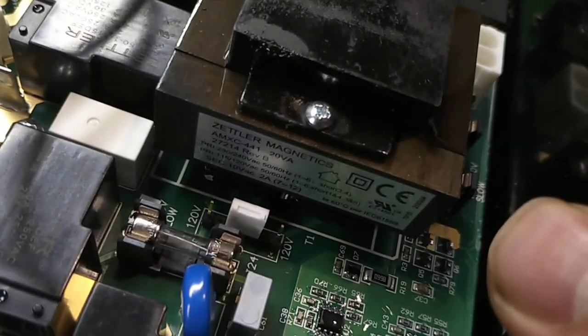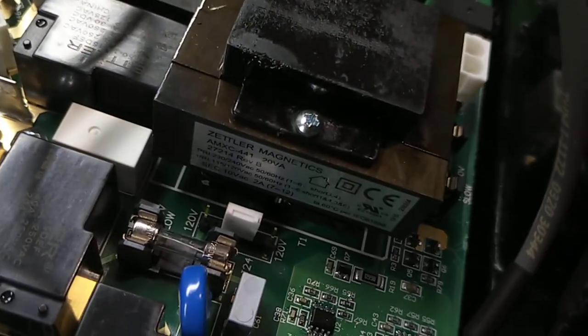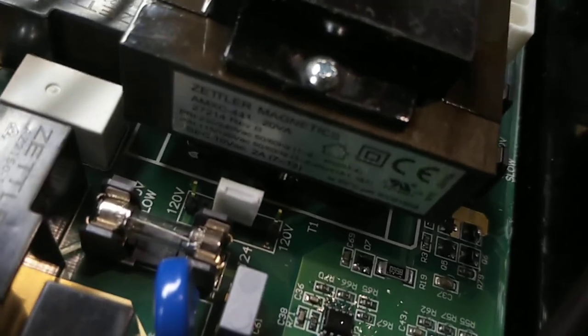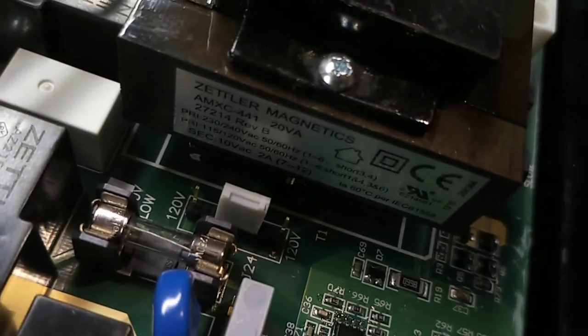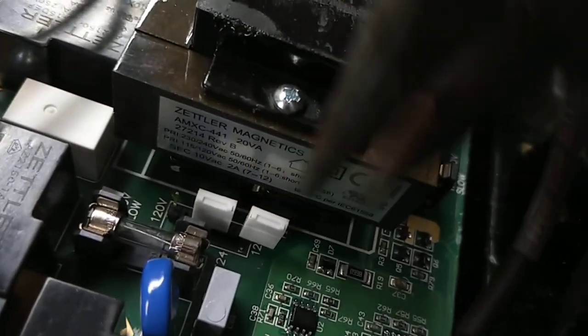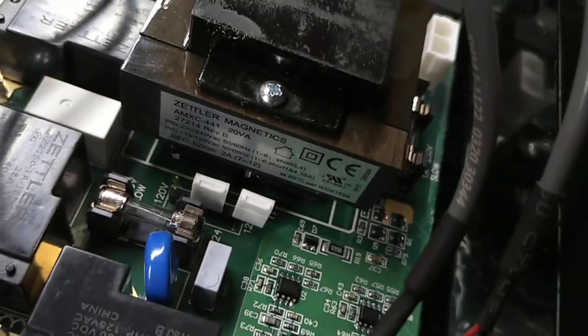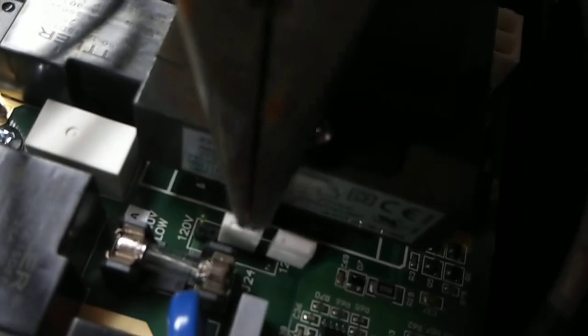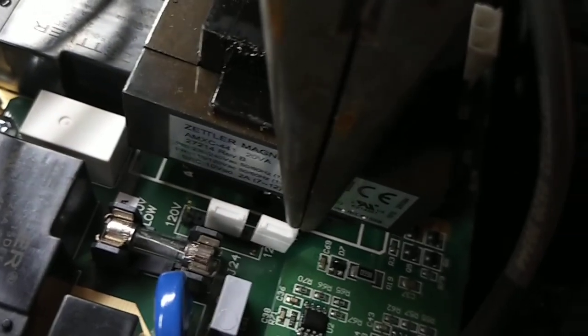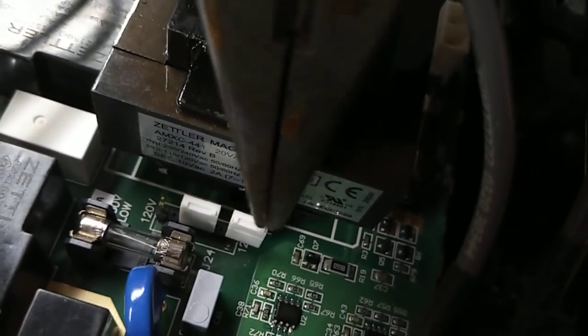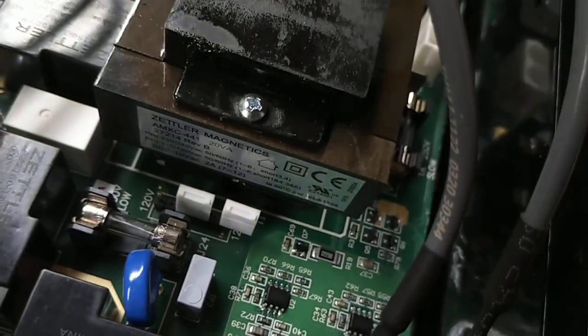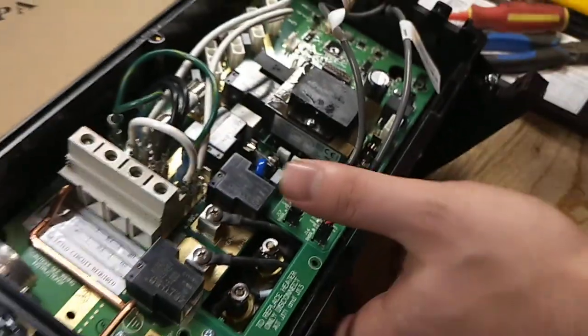We're going to jump the center two pins, leave the other two pins open. That's going to convert it for 240 volts. We now have an extra jumper pin. We're going to just put one of the leads on the one at the bottom and the other one not connected, so you don't lose that. So again, you're only jumping the two middle pins with one of these jumpers and this one, we're just going to put one of the empty ends on the end here so it's not jumping anything else, so we don't lose that again.